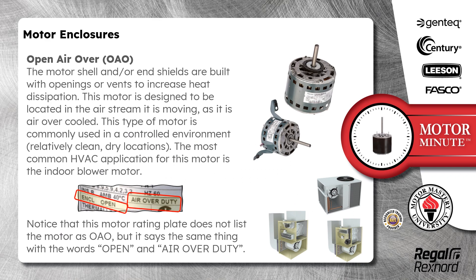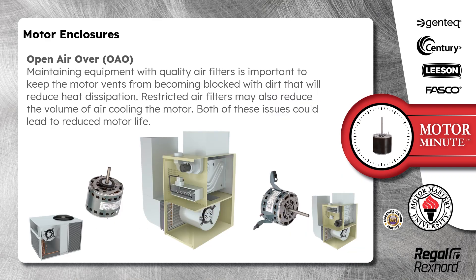Open air over, OAO. The motor shell and/or end shields are built with openings or vents to increase heat dissipation. This motor is designed to be located in the airstream it is moving, as it is air over cooled. This type of motor is commonly used in a controlled environment in relatively clean dry locations. The most common HVAC application for this motor is the indoor blower motor. Notice that this motor rating plate does not list the motor as OAO, but it says the same thing with the words open and air over duty. Maintaining equipment with quality air filters is important to keep the motor vents from becoming blocked with dirt that will reduce heat dissipation. Restricted air filters may also reduce the volume of air cooling the motor, and both of these issues could lead to reduced motor life.